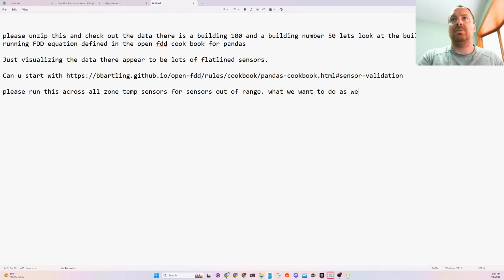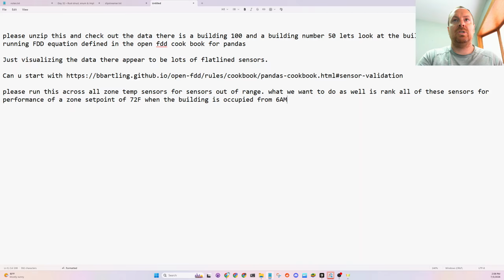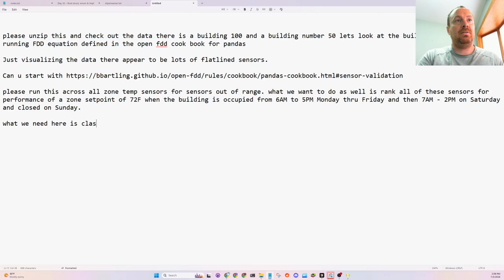What we want to do as well is rank all of these sensors for performance of, let's see, I think the client said of a zone set point of 72F when the building is occupied from 6 a.m. to 5 p.m. Monday through Friday, and then, let's see, I think they said 7 a.m. to 2 p.m. on Saturday and closed on Sunday.